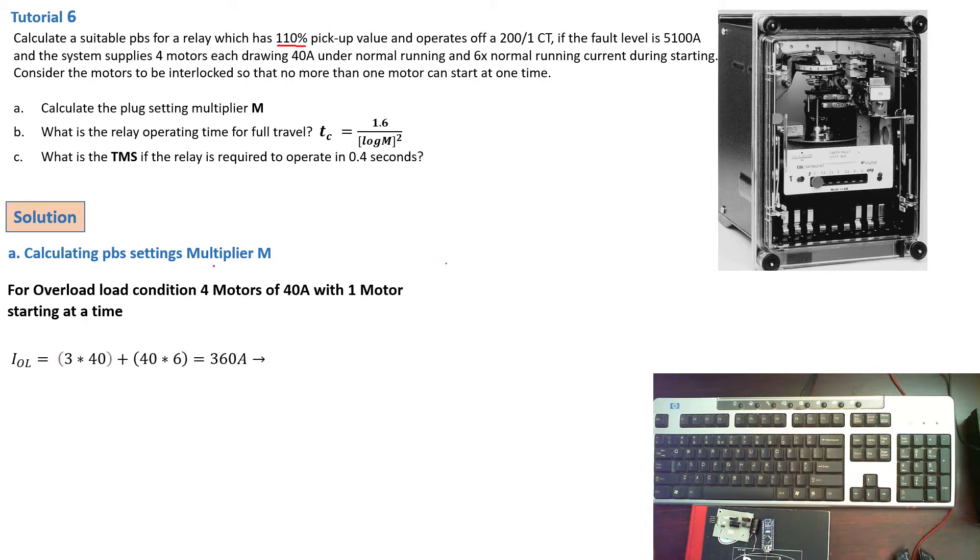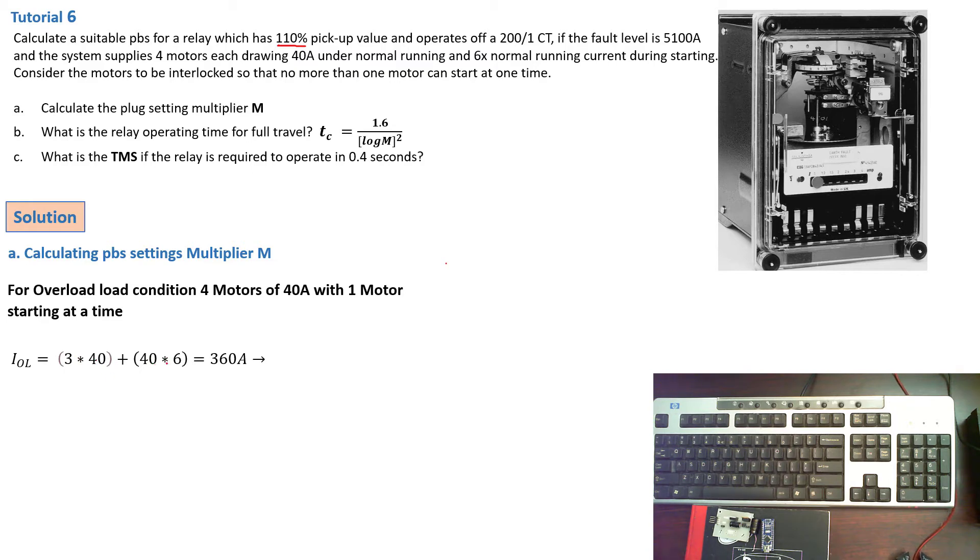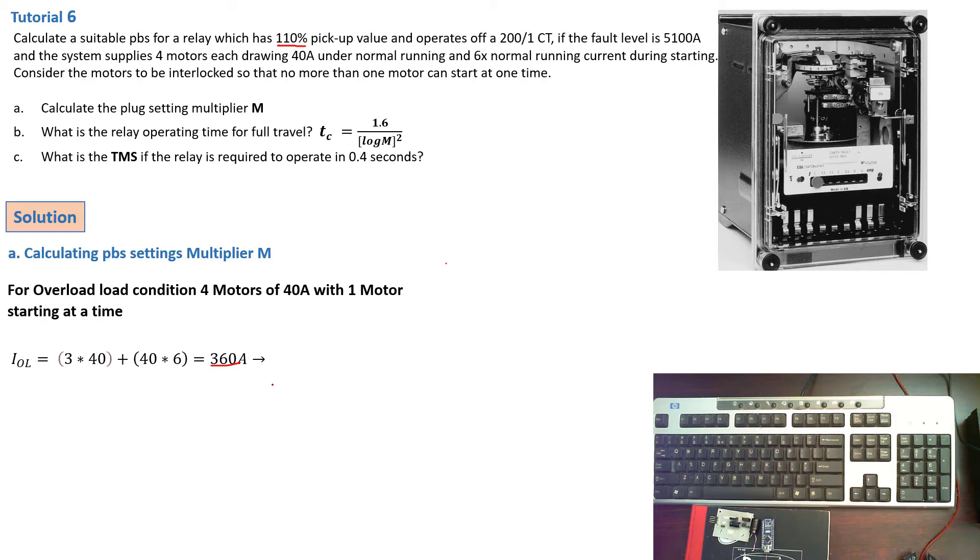So which means that condition will then be three times 40, that's the three motors running at 40 amps each plus one motor that is starting that will be 40 times 6, the starting current. And we're going to have a current of 360 amps.